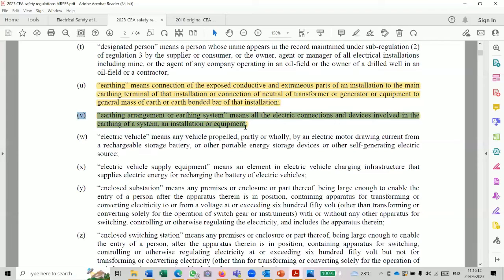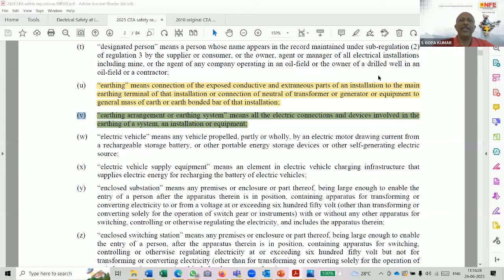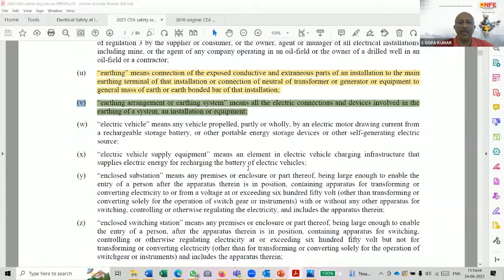So now that it is clearly defined as earthing system, what we can infer is it is only a redundancy. We did not give much weightage to the two separate and distinct earthing connections, because it has been given a new look in the new regulation. That's what I think. So I just put that part in the chat box. You can see the definition of earthing arrangement or earthing system. So you have to have two connections to the earthing arrangement or earthing system, meaning all the electric connections and devices involved in the earthing of a system, installation or equipment. So these two connections are actually to that part. Hope it's clear now. Thank you.